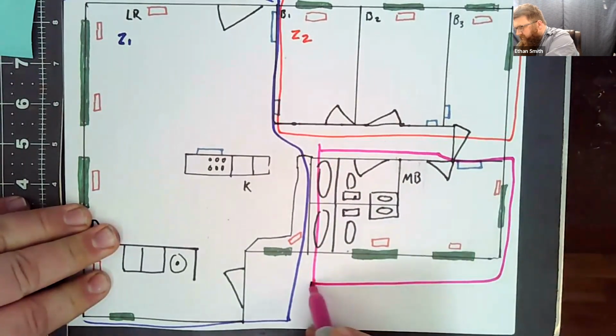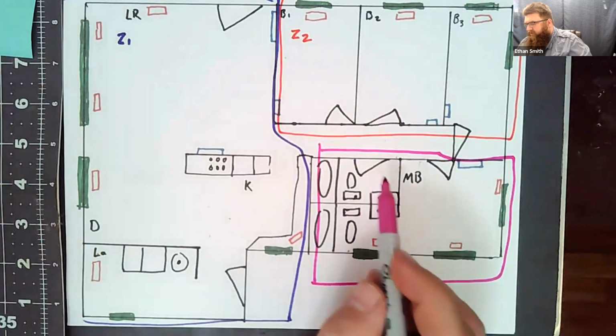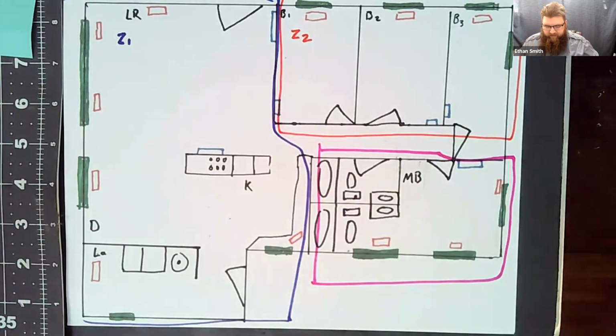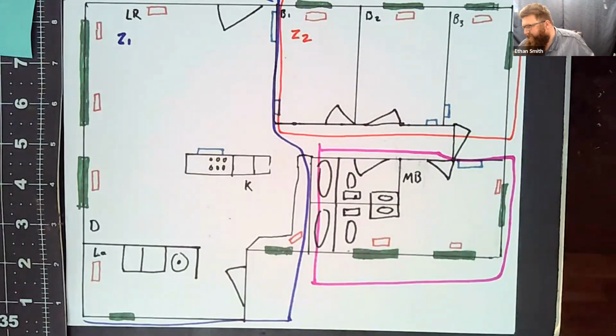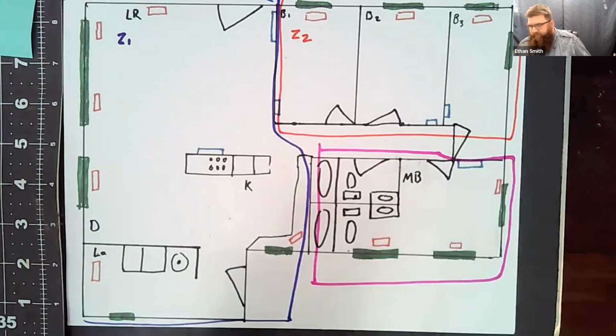By the way, some of you may notice a severe lack of a return or a supply in that bathroom, I should say. Turns out when you do the load on an interior bathroom, you can usually heat and cool it with a 3/8 inch piece of tubing. What exhaust fans are for. Forgot my zone 3 here.